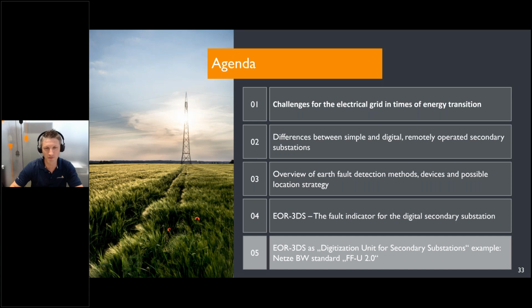Of course, there are further details I could mention, but we want to be finished in 1 hour. So in the end, I now want to show you the Netze BW standard FFU 2.0, where our device is used as an earth fault indicator. FFU 2.0 means in German: FF means remotely indicated and remotely controlled, U means secondary substation, and 2.0 indicates that there was also a first standard that was obviously not satisfying. So they made up a new concept, a second, improved, more sophisticated concept, FFU 2.0.